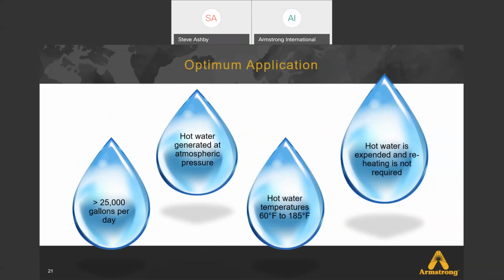So, optimum application for direct contact heating. Kind of use a jumping off point at 25,000 gallons per day as where it starts to justify the direct contact heating and the expense of it. Basically 25,000 gallons per day. We're talking over an 8-hour shift, about 50 gallons a minute. So that's, again, what you might use as a guide when you're investigating the use of direct contact heaters.